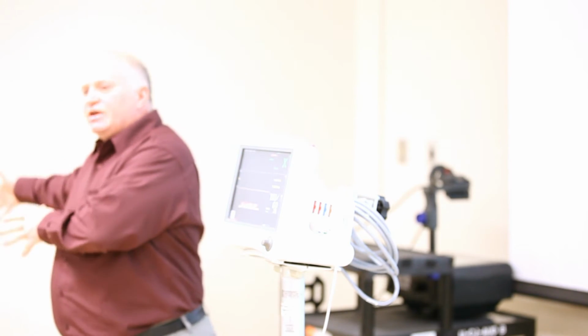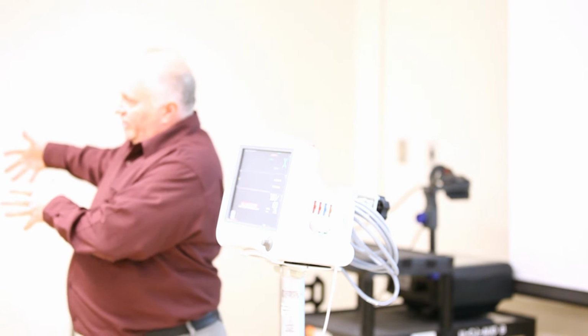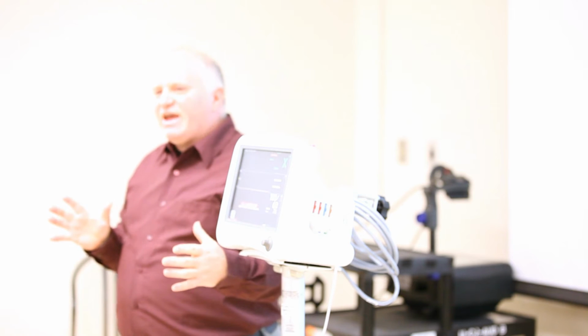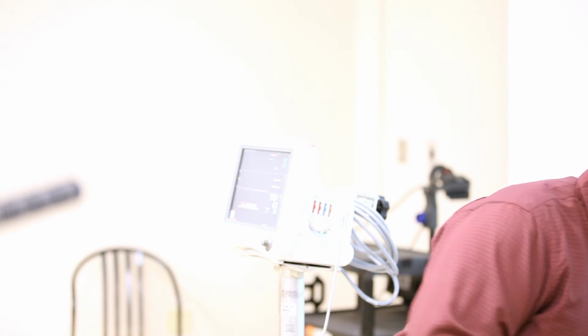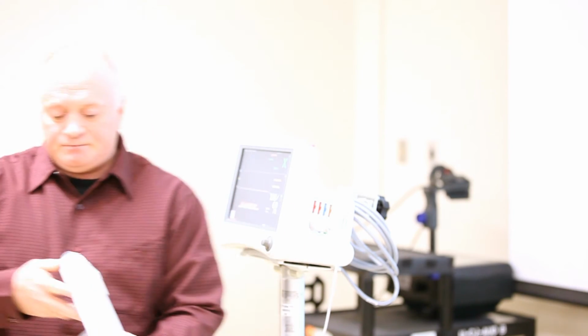For this one, if you'll notice, I plug the cable in. Now it has to warm up. Then we have to calibrate it, do a 2 to 3 point calibration. So we're looking at a 2-minute warm up, plus another reference cell to reference it to 0 and then to the normal CO2 range. So if we're in an emerge and somebody's tanking in the resus bay, or we're trying to do whatever procedure we want to do, you're going to have probably a 3 to 4 minute wait to get those numbers. It can be very frustrating for the clinician at the bedside to go through those steps.